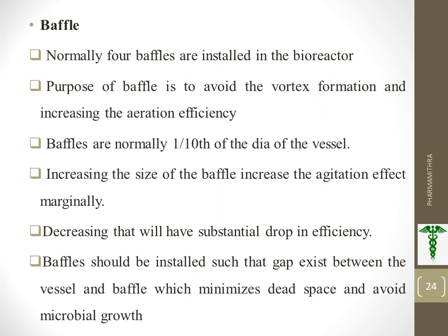Increasing the size of the baffle increases the agitation effect marginally. If you decrease the size of the baffle, that will cause a substantial drop in the efficiency of the fermenter. Baffles should be installed in such a way that a gap exists between the vessel and baffle, which minimizes the dead space and avoids microbial growth. So we want to consider this point at the time of placing.